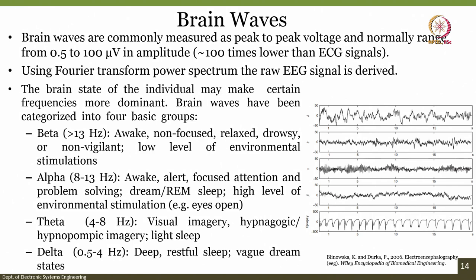Let us understand what each of these represents. Brain waves, as you can see from the slide, are commonly measured as peak-to-peak voltage. Normally the range of these brain waves is from 0.5 microvolts all the way to 100 microvolts. These are microvolts — 100 times lower than ECG signals, which are in millivolts. So sometimes it is a really very small signal, and for those who understand electronics, it is very important to design the module such that the signal-to-noise ratio is really high, so that we do not capture noise and miscalculate the signals.